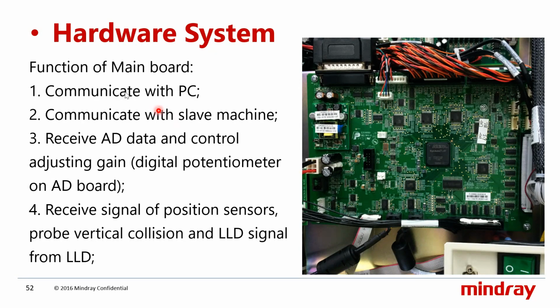So, functions of the main board. This board is communicating with the PC. Communicating with the slave machine means it is communicating with the drive PCB, and it receives the AD signal and controls the adjust gain. So the photometer preamplify PCB, the AD PCB, is there. From the AD PCB there is a signal line coming directly to the main board, which will maintain the adjusting of the gain, the auto correction of the gain.